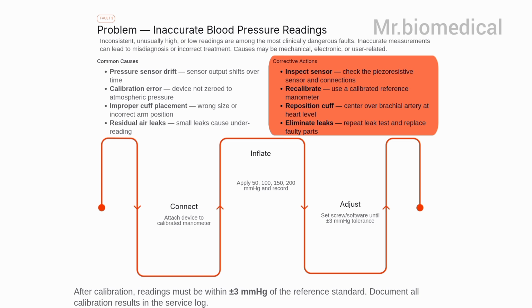As a service engineer, we perform calibration. We connect the monitor to a reference manometer and compare readings at different pressures such as 50, 100, 150 and 200 mmHg. The difference should be within plus or minus 3 mmHg. If it is more than that, then there is some issue. Can anyone tell me in the comment section why calibration is important in medical devices? Okay. Exactly, because patient safety depends on measurement accuracy. Never assume the device is faulty until you have checked cuff position and user handling.